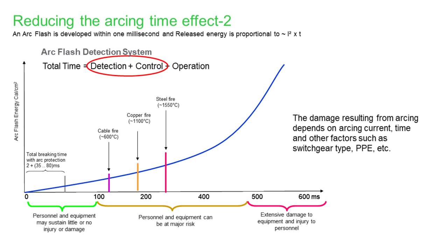Now we can look at the effect of time. As time increases, energy — which is approximately proportional to I²T — increases. After almost 100 milliseconds, cable will catch fire. With more time, copper will catch fire, and finally steel will catch fire. The amount of damage from arcing depends on current, time, type of switchgear, distance, and PPE used. If we are capable of removing the arc within 100 milliseconds, personal and equipment damage will be minimal. Longer times cause more damage. If we sustain more than 500 milliseconds, it will definitely result in expensive damage to personnel and equipment.